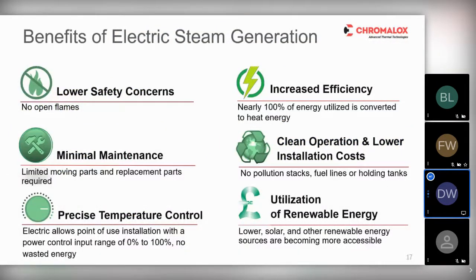So other ways that we can generate steam safely, efficiently, and sustainably is by using electrical energy, by using power to convert to thermal energy. And this is where one of our subsidiary companies that I introduced previously, Chromalox, come in. So if we can use one of their electrical elements to generate steam from electricity, then some of the benefits that we have are, well, there's no open flame to consider. And if there's no open flame and no heat pipes to consider, there's no risk of that steam boiler overpressurizing if there were to be a catastrophic failure.